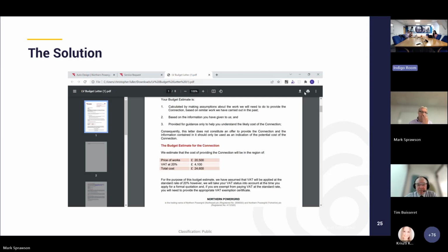This can also be done at medium voltage. UK Power Networks, who cover London and the southeast of England, now do this at MV using this tool. It's a more complex user interface since there's more to think about at MV, but it does full backfeed analysis, looking at N-1 running configurations, voltage, load, and fault level perspectives, with full load assessment. If the connection requested is less than 1 MVA and the price comes out at less than £200,000, that connection is offered firm to the customer without an engineer ever looking at it. The trust built into these systems has become very high, and they're happy to push through connections up to £200,000 without checking them. Only above that threshold does it go past an engineer for a verification loop.